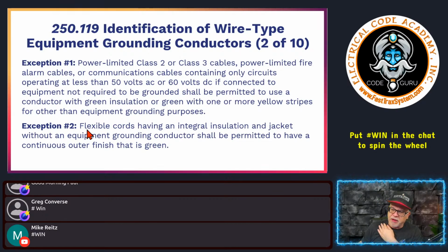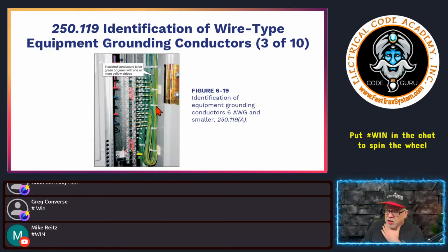Next, flexible cords. It says flexible cords having integral insulation and jacket without an equipment grounding conductor shall be permitted to have the continuous outer finish that is green. Okay, so you have some allowances for a flexible cable, and there are also applications where it's a double insulated type of cord, and the outer finish of the cord itself is green. And it doesn't have an equipment ground inside of it. It might be double insulated, integral to the insulation type of scenario. So, all right. Here we go.